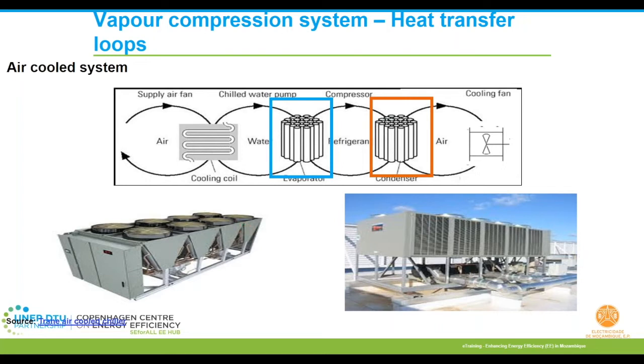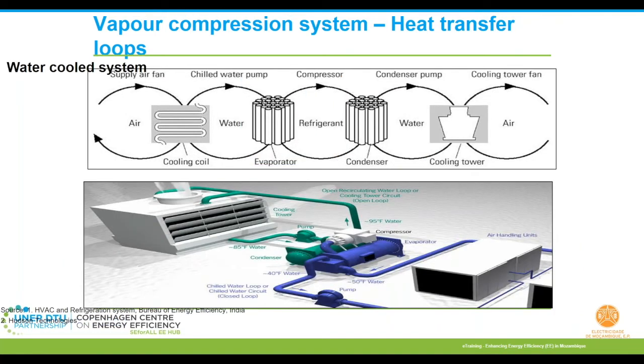These types of air-cooled systems are usually used in areas where there is water scarcity or strict water regulations. If water is not a problem, then people can go for the higher capacity water-cooled systems. Again, the fundamental components remain the same, that is, the evaporator and the condenser. Only the medium of heat exchange changes. Here, even on the condenser side, heat exchange is done with water, and you will have another additional component called cooling towers in place.